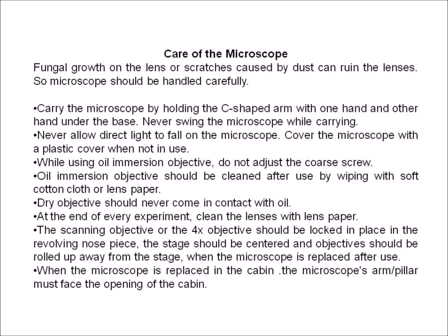Never allow direct light to fall on the microscope. Cover the microscope with a plastic cover when not in use. While using the oil immersion objective, do not adjust the coarse screw. The oil immersion objective should be cleaned after use by wiping with a soft cotton cloth or lens paper. The dry objective should never come in contact with oil. At the end of every experiment, clean the lens.